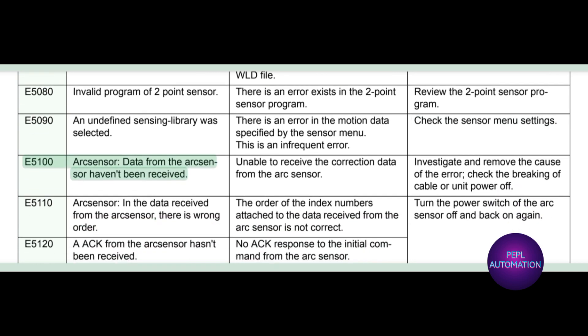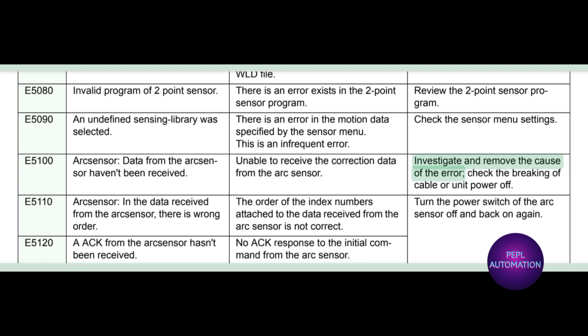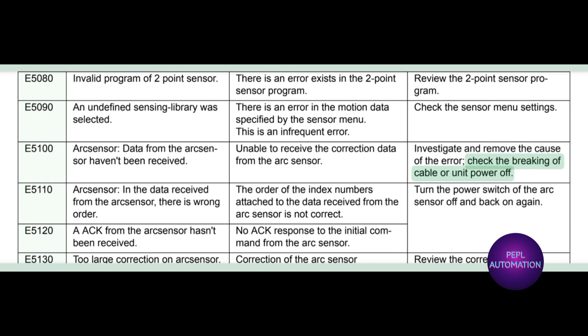E5100 arc sensor: data from the arc sensor have not been received. Unable to receive the correction data from the arc sensor. Investigate and remove the cause of the error. Check the breaking of cable or unit power off.